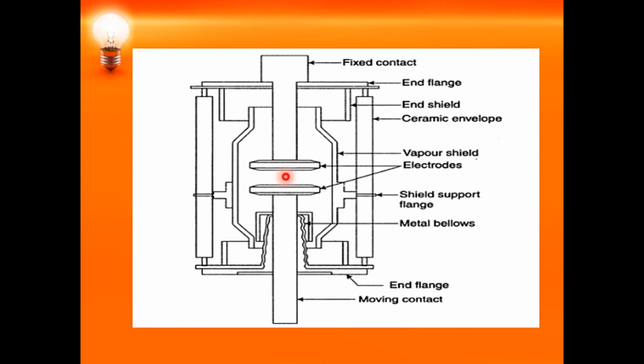And where does it find application? These are useful as very high speed making switches in many industrial applications, and they can be used to interrupt wherever the voltage is very high and the current to be interrupted is very low. Usually the voltage range for which this vacuum circuit breaker is used is 11 to 33 kV. So this is all about the vacuum circuit breaker.